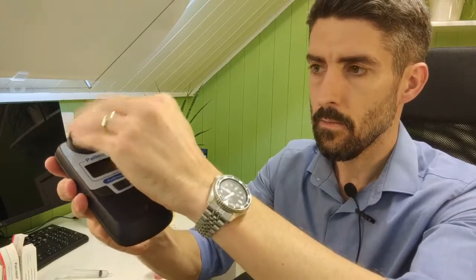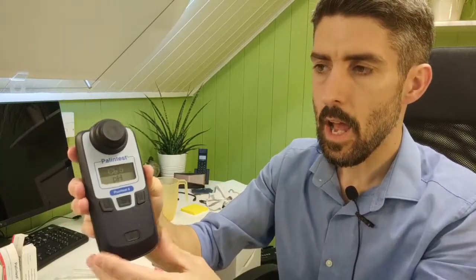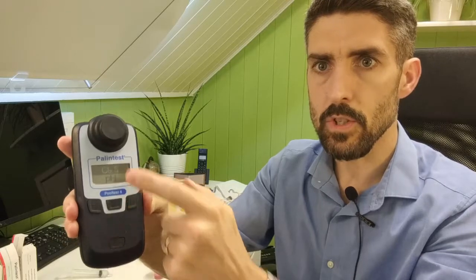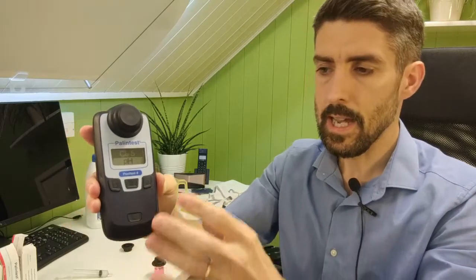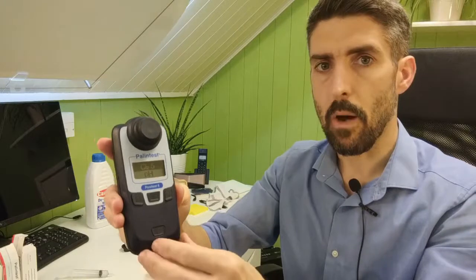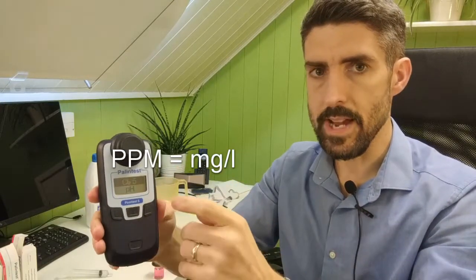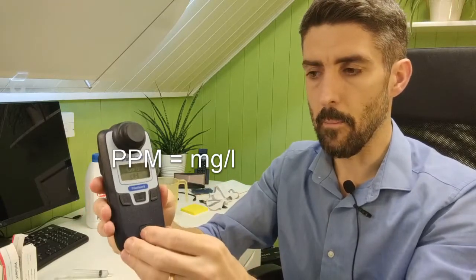So put it in, turn the unit on with the on button, and it will default to chlorine. Make sure that the test tube is all the way in because the lid is designed to shroud out any ambient light. It'll come on at chlorine. Cl2 is the symbol for chlorine. The 5 denotes that this particular photometer is able to measure up to 5 parts per million. If there's a greater amount of chlorine than that, it'll come up with a greater than 5 symbol.